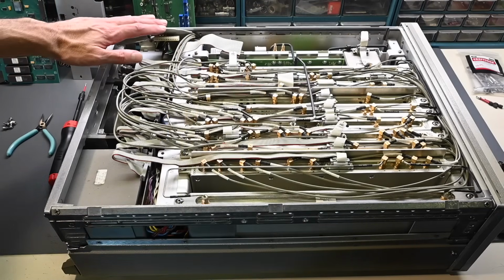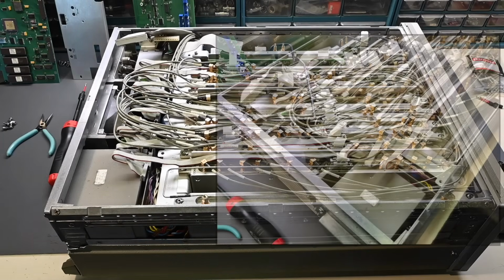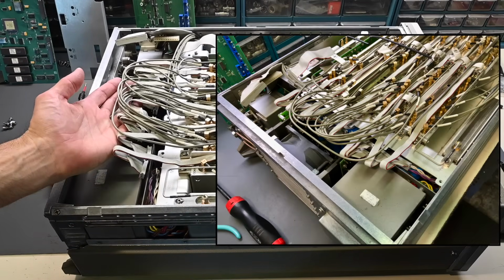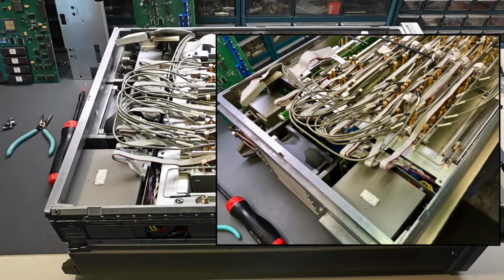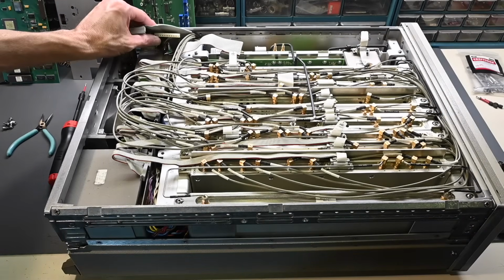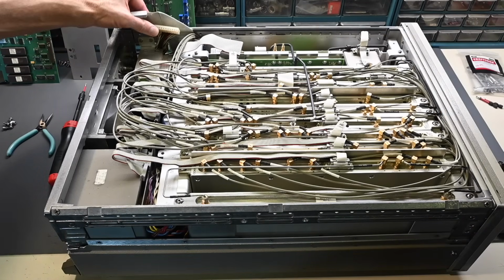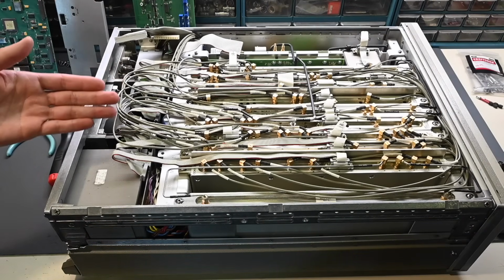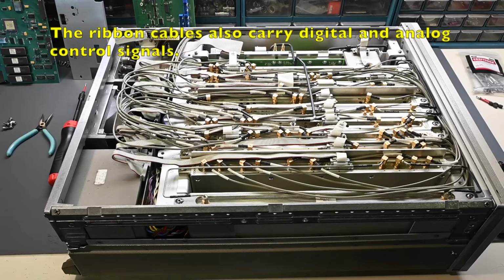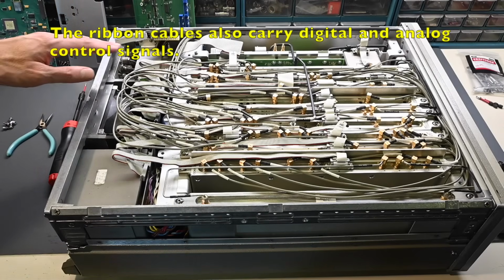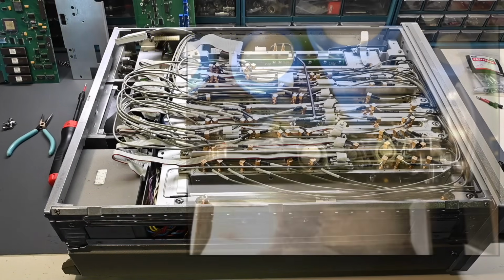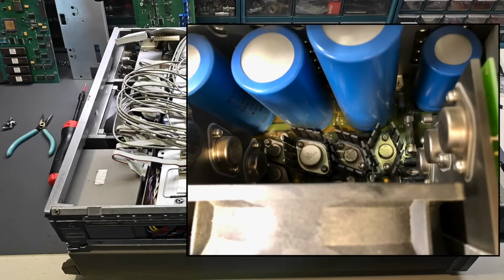I also removed the board that fits along this area of the instrument. And all these ribbon cables plug onto that board, and among other things on this board, it's a lot of main power distribution. So you can see some very heavy gauge wire that comes up to this connector, so that's distributing the power across to those ribbon cables, and then the ribbon cables are going up to each module. So with this circuit board out of there, I have access down to the cooling fan and other components in the power supply section, so I can clean out the dust that's accumulated back here.